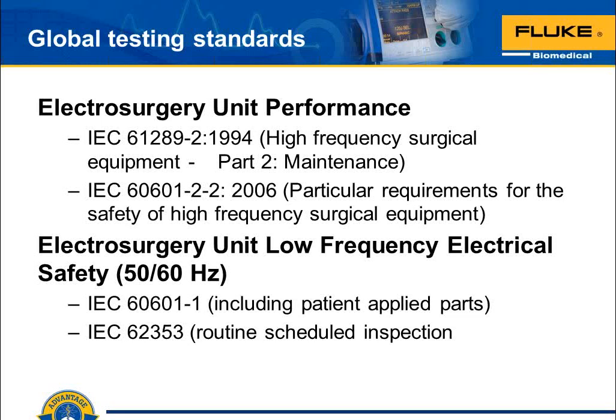So hospital biomedical engineering and clinical engineering departments and third-party providers generally follow the ESU manufacturer's model-specific inspection and testing procedure. That's found in the service manual for each model of ESU. But we can often look to the IEC standards for guidance as well, just to be sure, or if there's any question. And that's what we do here at Fluke Biomedical when we're trying to make sure that the design of our test equipment is going to adequately test the medical device. We certainly recommend that you do take a look at that. There are some other alternatives if you can't get access to the model-specific inspection procedure. We'll talk about that in a little bit.